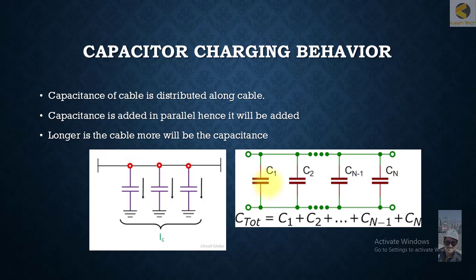Since capacitances are added in parallel, if the length of the cable or testing equipment increases, the capacitance will keep on increasing. So if you are testing a shorter cable versus a very long cable, the very long cable will draw more charging current and will take more time to get charged.